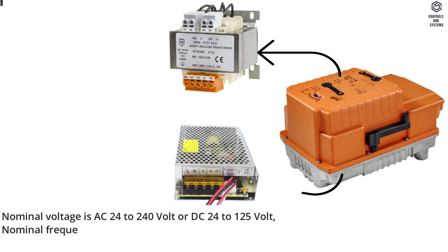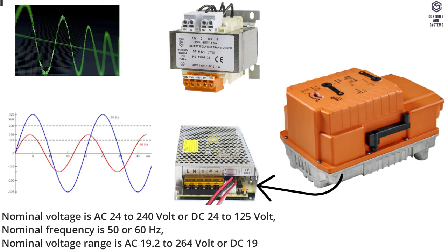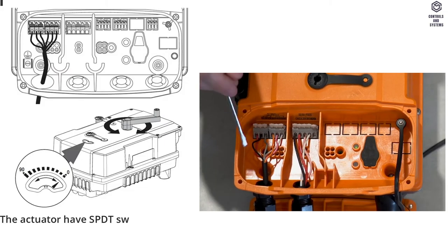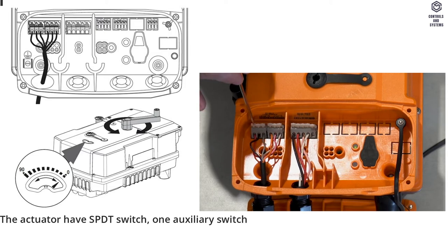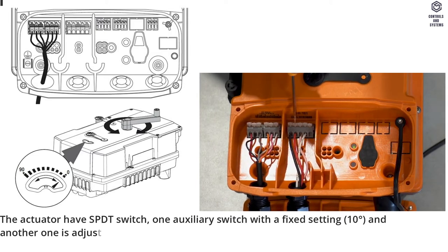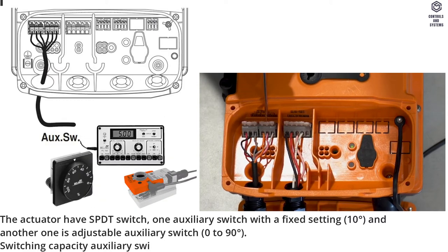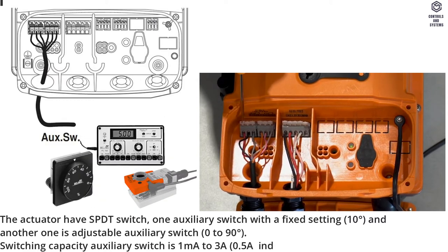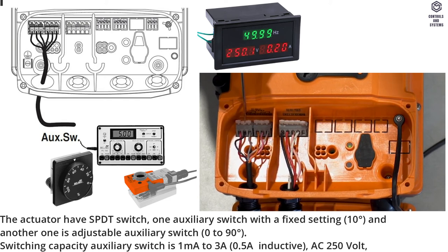Electrical Data: Nominal voltage is AC 24 to 240 Volt or DC 24 to 125 Volt. Nominal frequency is 50 or 60 Hertz. The actuator has an SPDT switch — one auxiliary switch with a fixed setting at 10 degrees, and another adjustable auxiliary switch from 0 to 90 degrees. Switching capacity for the auxiliary switch is 1 milliamp to 3 amps, 0.5 amps inductive, AC 250 Volt.